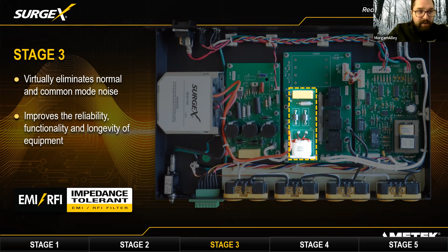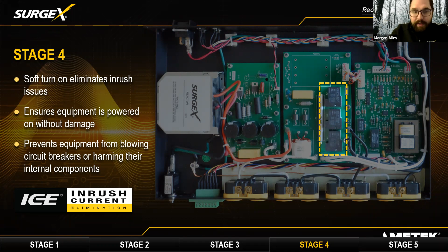We have ICE, designed to protect devices from inrush. You can think of inrush as when a product turns on, it'll have a really sharp pull of power, a really sharp draw as it turns itself on. ICE we liken to a soft close door. Instead of slamming the door shut and having this big event, all of that same power comes in, but it slowly gets turned on. So as all those capacitors are pulling in power, we use ICE to reduce that additional wear on equipment that naturally happens whenever electronics get turned on.